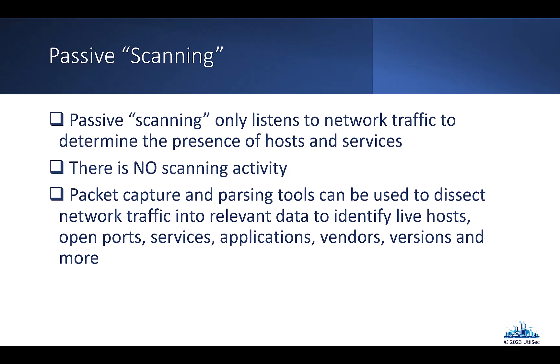But the advantage when talking about network listening or sniffing is we're gathering that traffic, it's not active scanning. So we don't have a potential for breaking things. We're not putting those network packets out which could potentially interfere with a system, especially those older industrial control assets like older PLCs that we don't want to touch.